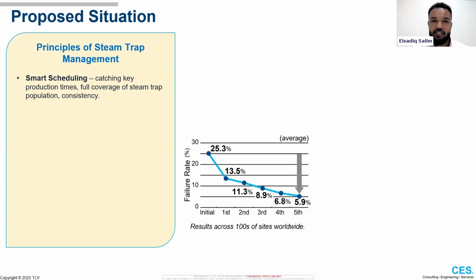First and foremost is smart scheduling. So if you've got X number of steam traps on site and you have an annual survey every year, say April 20th, you might not catch all of those steam traps on that survey, or some steam traps will be on an irregular load. We typically have a winter load and a summer load, so you want to make sure you schedule such that every steam trap is tested consistently.